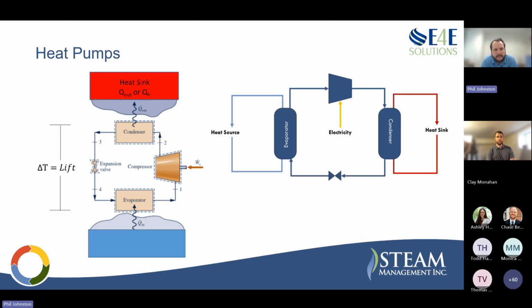Going back to what Clay said about lift, that's a very important part of this. It drives the electrical consumption of the compressor or the heat pump, and drives the performance and efficiency. So when you're thinking about work put into the system from an energy standpoint, it's really that compressor, lifting the heat from the low temperature in the evaporator to the high temperature in the condenser. This is really driven by pressure. The compressor takes that low temperature, low pressure gas, and pressurizes it and heats it up at the same time, to the high temperature, high pressure gas that goes through the condenser.